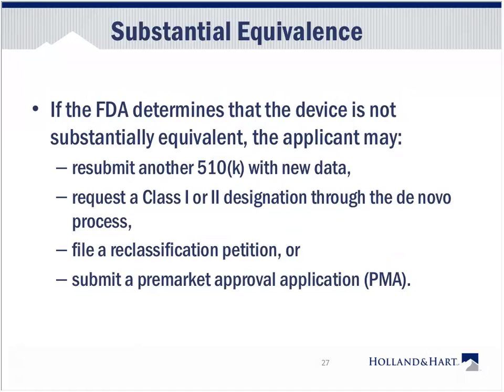So basically, if the FDA comes back and says your device does not meet a predicate device, and in fact is such new technology that there's nothing out there to use as a predicate, you are basically stuck with going through the pre-market approval process. Again, that's typically not the course we want to take because it is time-consuming and very, very expensive, labor-intensive.